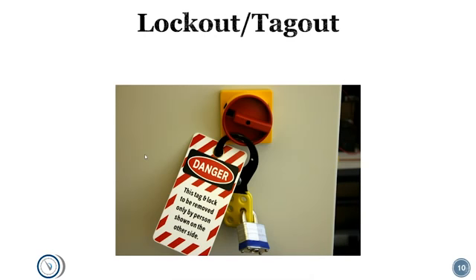I don't care if you're residential or commercial, because even in residential, you may do multifamily where you have to go between floors and work on equipment that you're shutting off where you're not line of sight to the disconnect. What a lockout tagout setup does is allow you to independently lock a piece of equipment off at the disconnect so that you're the only one with the key who can unlock it to turn it on. And you can potentially put multiple locks in the lockout tagout lock. That way, if more than one person is potentially working on the equipment, you're all going to be protected. Everybody has to unlock it before the equipment can be turned on.